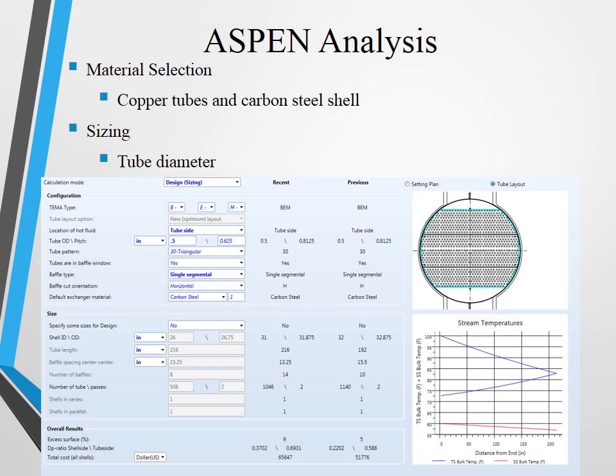The material of construction for the shell was made to be carbon steel because of its relatively cheap price compared to other metals. The tubes were specified as copper because of its high thermal conductivity when compared to carbon steel. Copper also has better corrosion resistance than carbon steel. Utilizing copper raises the price, but comes with the benefit of better heat transfer and mechanical properties. The geometry of the heat exchanger was determined by selecting a standard tube size of 1/2 inch and packing them together efficiently with a 5/8 inch pitch and a 30-degree triangular configuration.